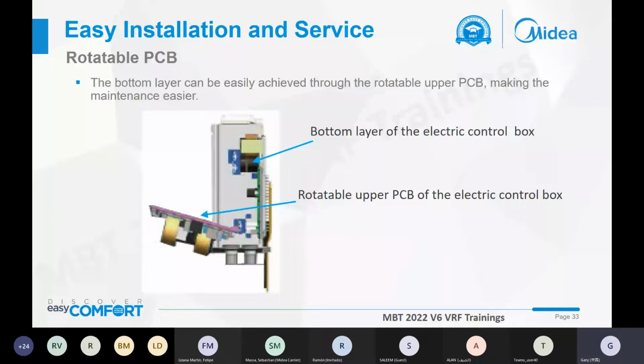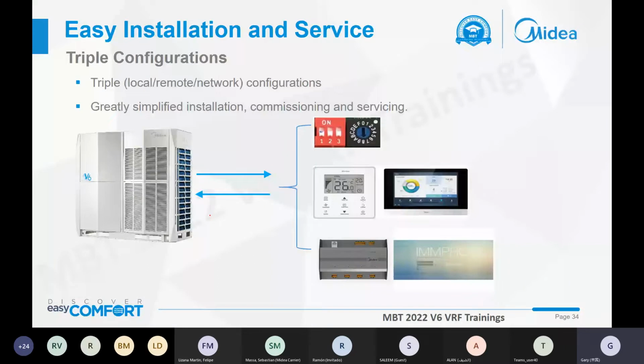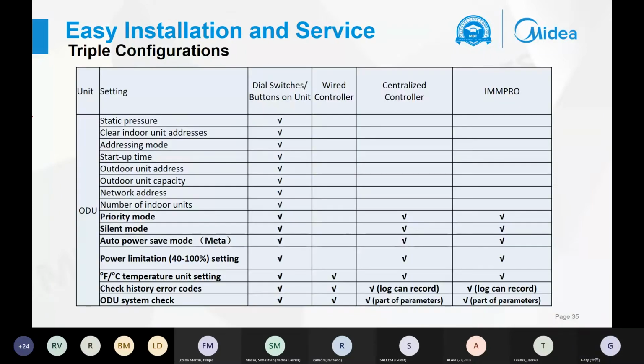And for the triple configurations, we can set different functions, the network address, or the BMS from the dial switch on the outdoor unit PCB. We can also select from the wire controller or the centralized controller. We can also set them from gateways like BMX or the BMS systems, IM or IM Pro. It greatly simplifies installation, commissioning, and servicing. This table shows the different ways to set the different functions.